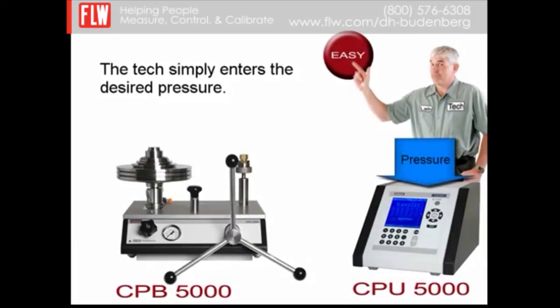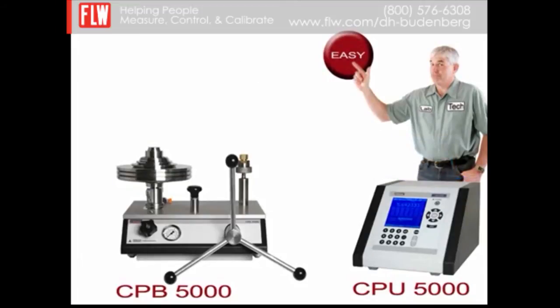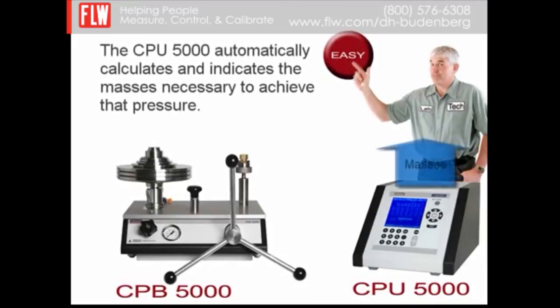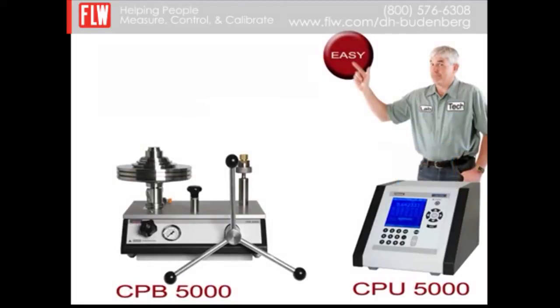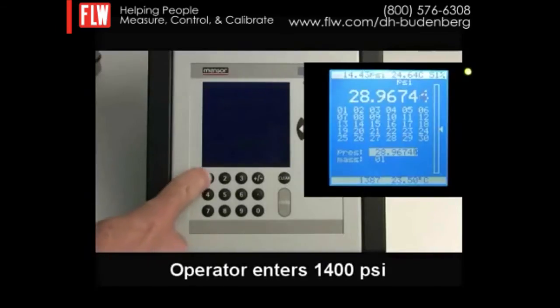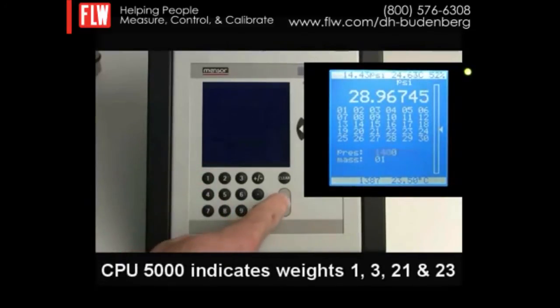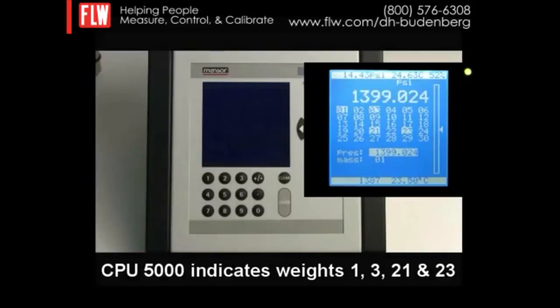The technician simply enters the desired pressure. The CPU5000 automatically calculates and indicates the masses necessary to achieve that pressure. In this example, an operator enters in 1400 psi and masses 1, 3, 21, and 23 are indicated.